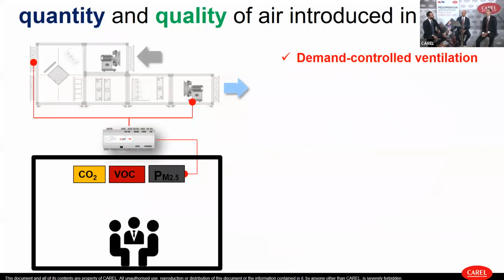So taking a look in deeper detail at which are the important strategies that we have to take into consideration, the first one that we can mention is the demand control ventilation. Demand control ventilation means that we want to introduce the right amount of air inside the confined space according to some sensors that are able to measure the CO2, VOC, or PM 2.5 inside our confined space. So regulating the speed of the fan, regulating the damper is an important strategy, because in this way we are sure that we are introducing the right amount of fresh air inside the confined space that is required by the number of people that is present inside that space.